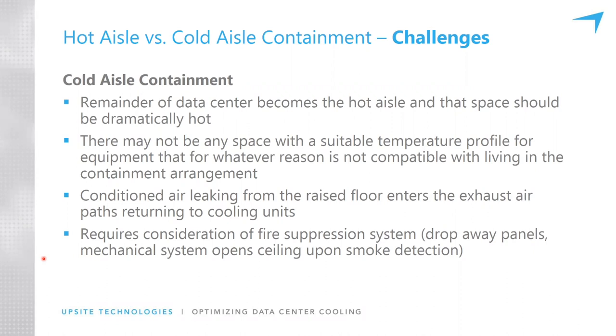Or if you do cool it by putting in a supply tile, then it somewhat compromises the overall design of the solution and requires consideration of fire suppression. So you need either drop away panels or a mechanical system to open the ceiling upon smoke detection. There's a number of issues around fire suppression.